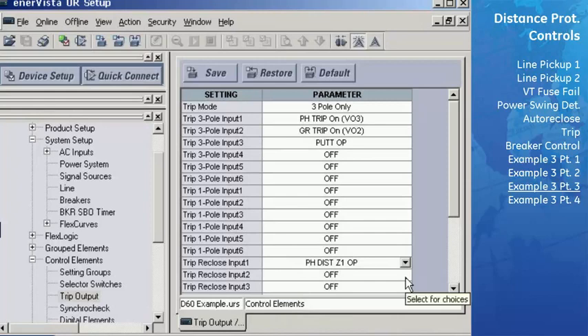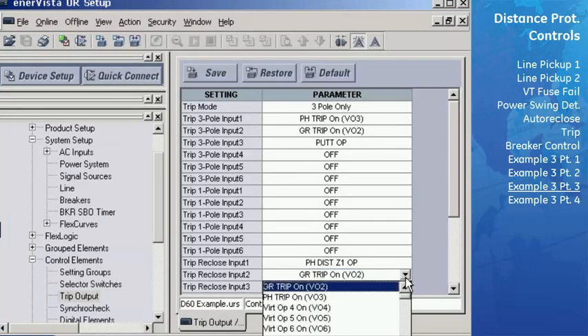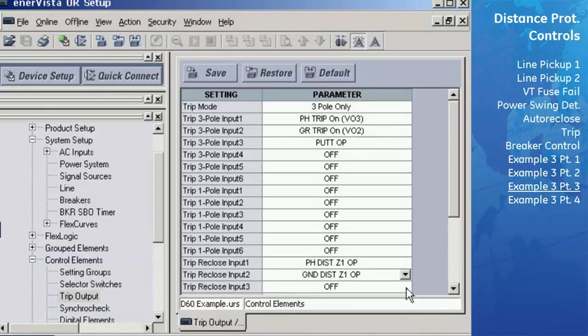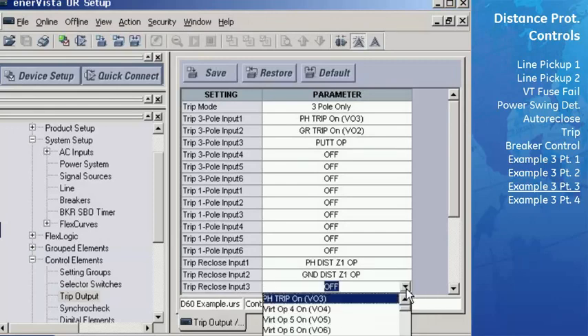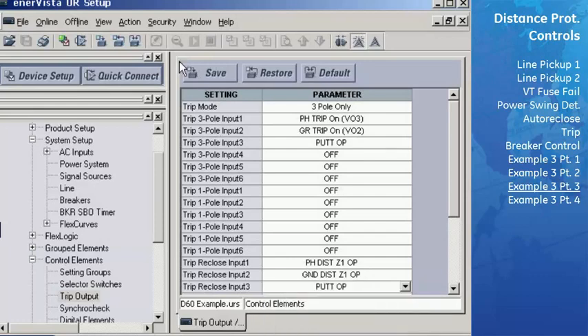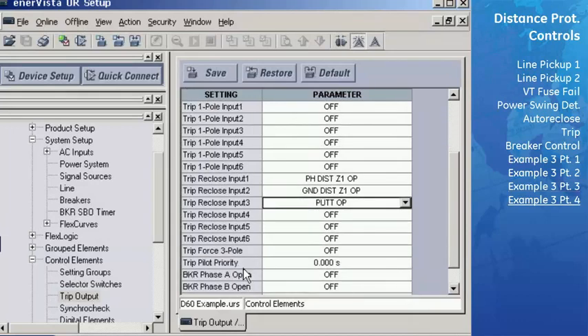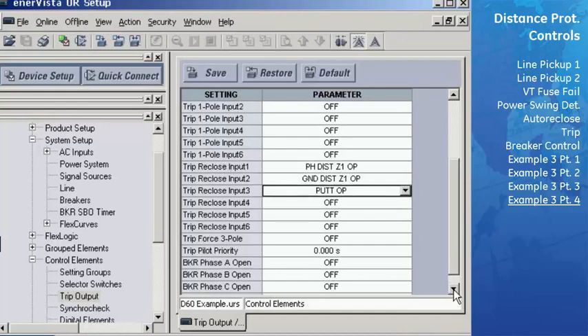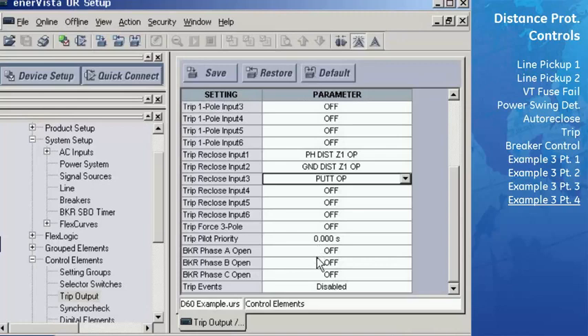Select Ground Trips or Virtual Output 2 for Input 2. This signal was also created in Example 2 and will turn on if any ground distance zones operate. Select PUTT Operate for Input 3 to ensure a 3-pole trip occurs for a PUTT scheme operation. The trip pilot priority can be left as 0 seconds. The breaker status inputs were configured in the breaker control function and therefore do not need to be assigned here.